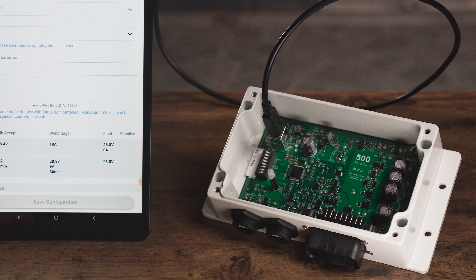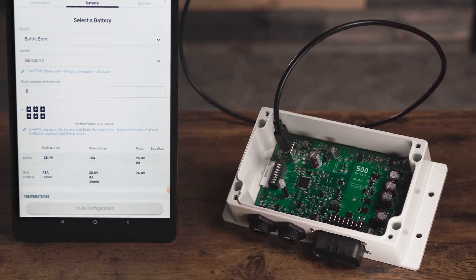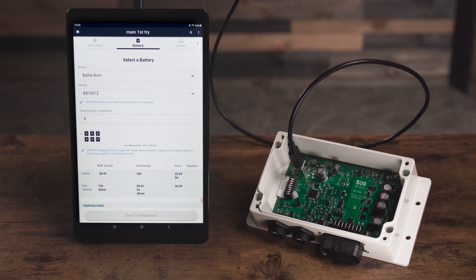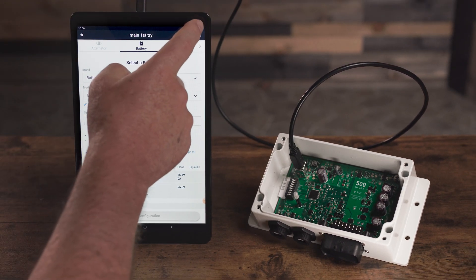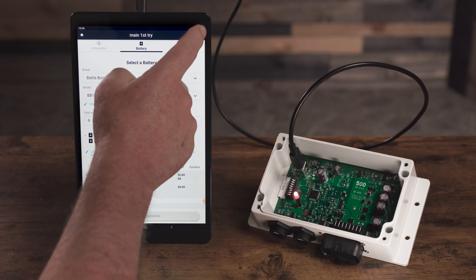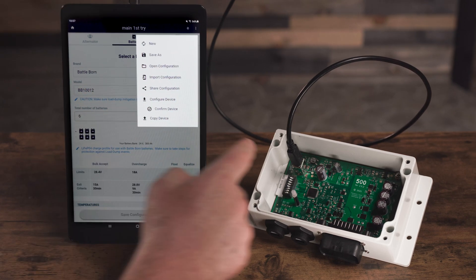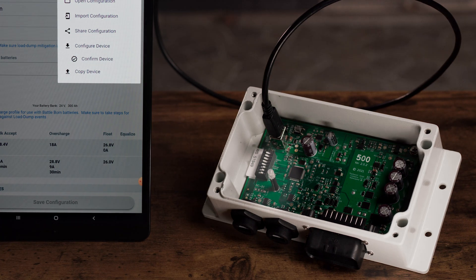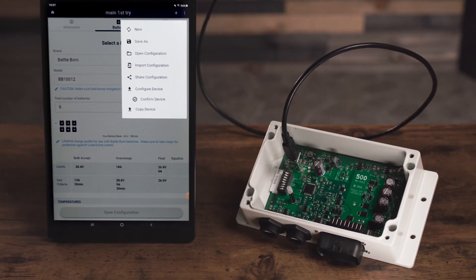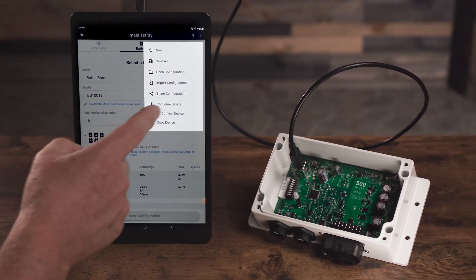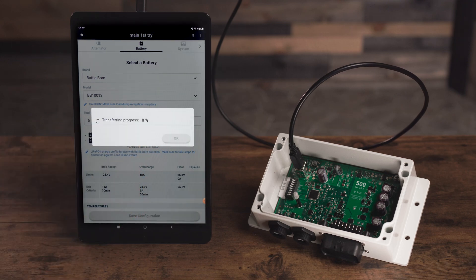This fault code will prevent you from being able to send a configuration to the device. So what we recommend when you're getting ready to transfer a configuration is to first press the reset button. This should be a quick press, not a long press. Wait for the green light to blink and then go ahead and configure the device before the regulator faults again.